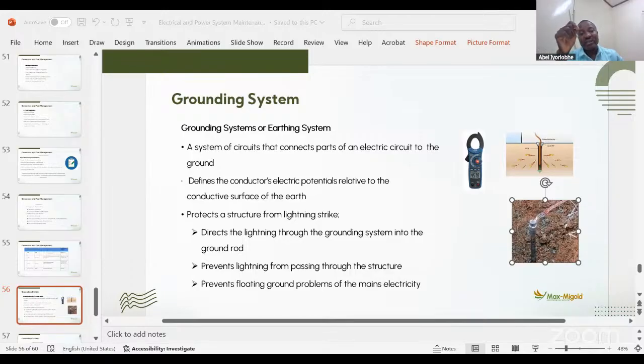Resistivity, you put it on resistance, you test it. You have a value that should not be more than 2. If it's going above 2 around that place, you know that region needs to be improved with what I've mentioned to you: the charcoal, the salt, and the animal waste. So if it's voltage, the same thing, you put it on the voltmeter, because a megger is also a multimeter. You put it on the terminal and the body of where you want the earth to be measured. You set them aside and it will give you the exact figure that you require around that place. Maybe when you go on trip, you will see it live. So that is how it is done.